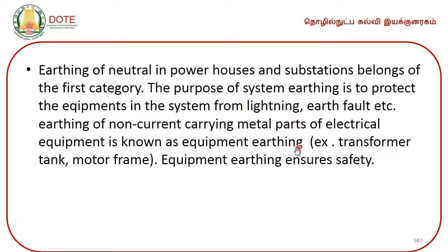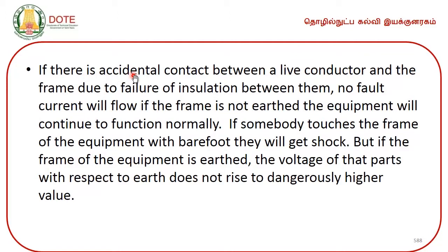Example: transformer tank, then motor frame. Equipment earthing ensures safety. If there is accidental contact between a live conductor and the frame due to failure of insulation between them, no fault current will flow. If the frame is not earthed, the equipment will continue to function normally. If somebody touches the frame of the equipment with bare foot, they will get shock.